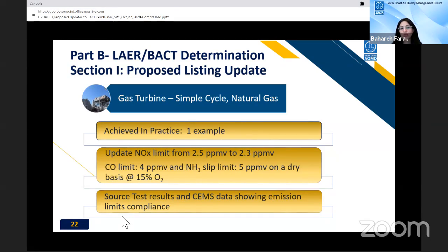And this, again, 2.3 ppm limit is during the normal operation, not during the startup, shutdown, and maintenance periods, because again, these are the peaker units, so there is a lot of fluctuation when they're starting, and we have to filter out a lot of those startup and shutdown numbers. And the RATA test results, as well as 1 hour CEMS data, show that they are in compliance with permit limits for NOx and CO. And based on the inputs from engineering and permitting staff, and looking at the CEMS and also the source test, this will be an achievable limit and the requirement for future gas turbines of this type, but just for the major sources for now.